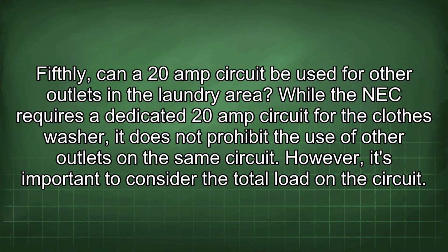Fifthly, can a 20 amp circuit be used for other outlets in the laundry area? While the NEC requires a dedicated 20 amp circuit for the clothes washer, it does not prohibit the use of other outlets on the same circuit.